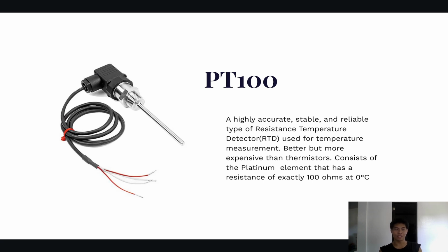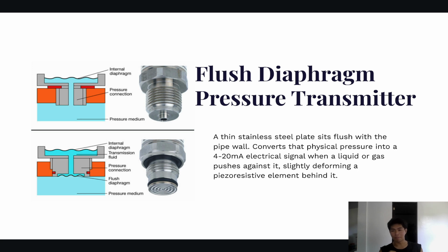Proceeding on to the flush diaphragm pressure transmitter for the pressure variable. It is a stainless steel plate that sits flush with the pipe wall. It converts physical pressure into a 4 to 20 milliampere electrical signal when a liquid or gas pushes against it, slightly deforming a piezoresistive element behind it. It has a transmission liquid which is triggered when the pressure of the liquid beverage makes physical contact with the flush diaphragm pressure transmitter.